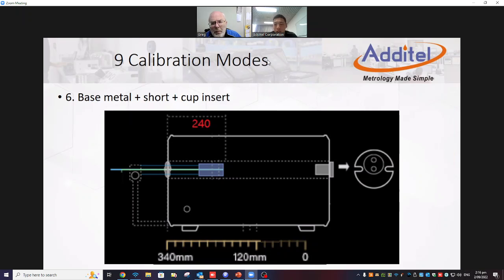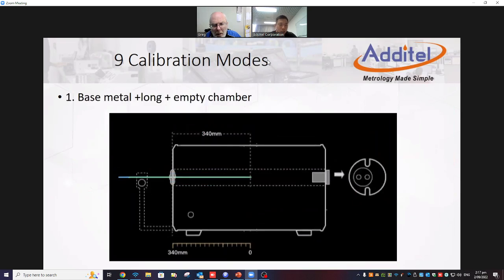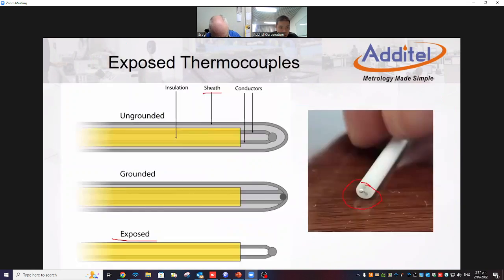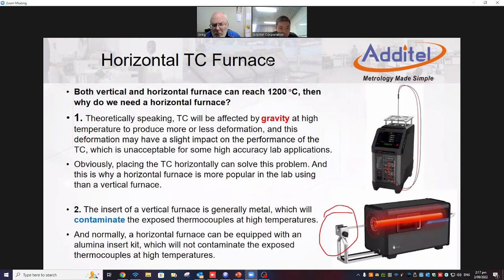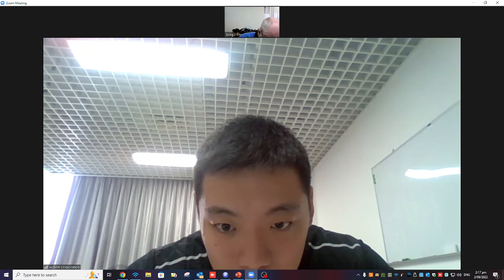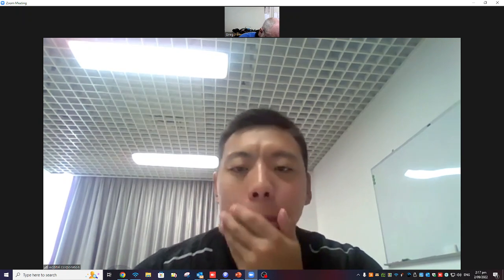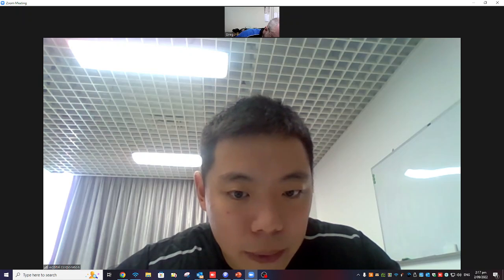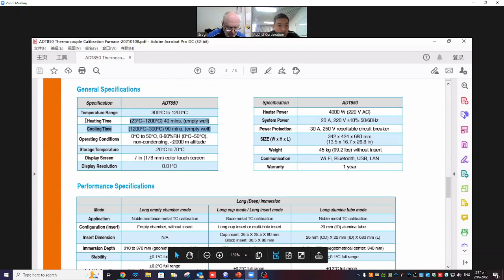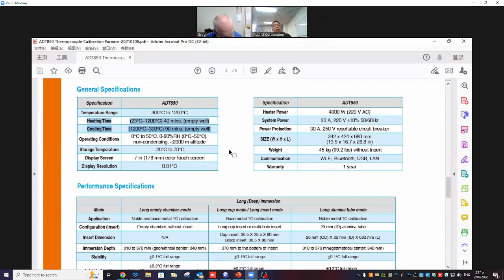What is the heating time from ambient to 1200? Let me check the data sheet real quick. Yeah, the heating time is 40 minutes from room temperature to 1200. Cooling time is 90 minutes from 1200 to 300 degrees Celsius. The temperature range of the furnace is from 300 to 1200.